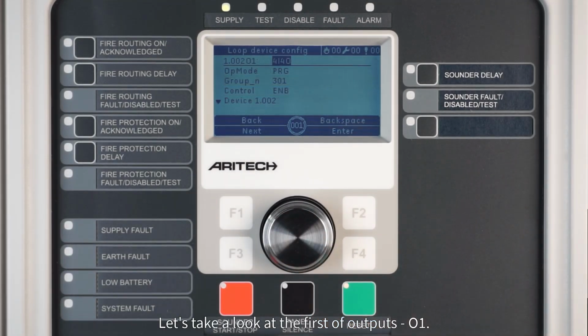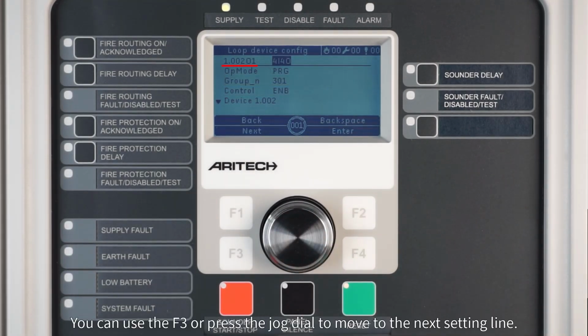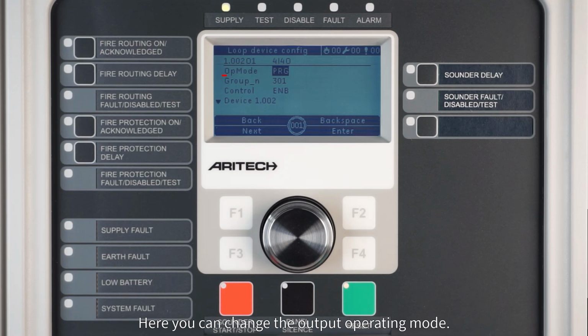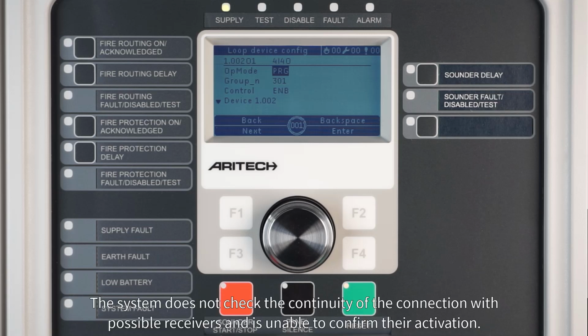Let's take a look at the first of the outputs, 01. You can use the F3 key, or press the jog dial, to move to the next setting line. Here you can change the output operating mode. Please note that the outputs on the module are not supervised. The system does not check the continuity of the connection with possible receivers, and is unable to confirm their activation.